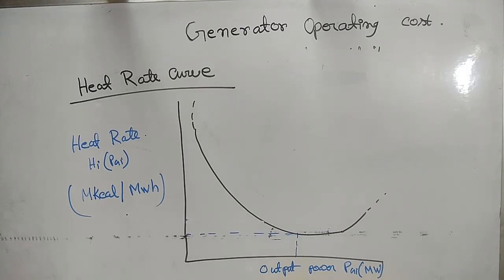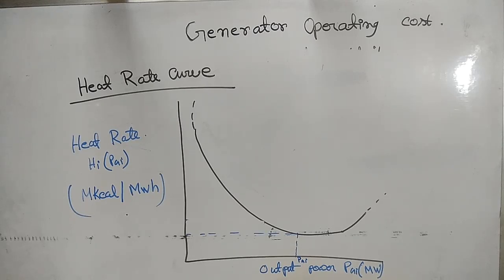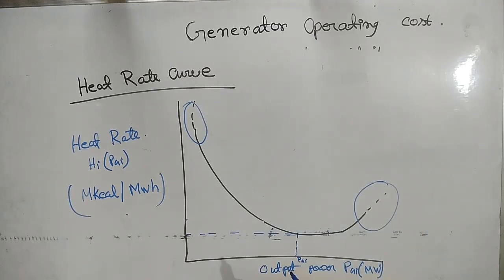The generating unit efficiency can be defined as the ratio of electrical energy output generated to the fuel energy input. So the generating unit is most efficient at minimum heat rate, which corresponds to a particular PGI. The heat rate or efficiency varies with the output power, and the curve indicates that it increases — meaning drop in efficiency — at high and low power limits. Typically, the peak efficiency heat rate of a modern fuel power plant is around 2.5 M kilocalorie per megawatt hour.